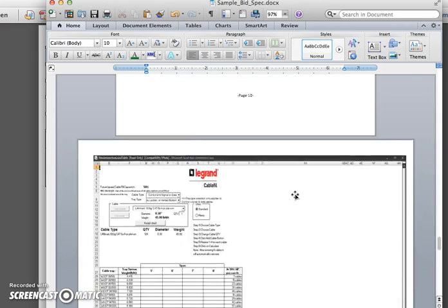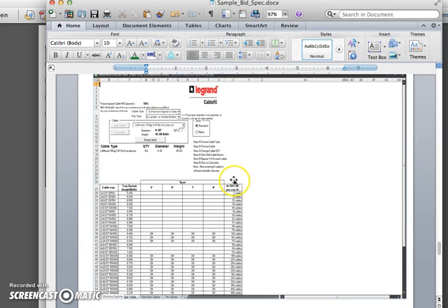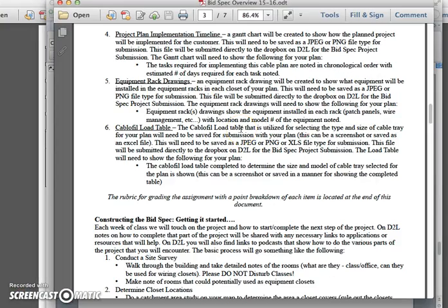And this student, I believe, had it, actually it's right here. Here's a copy of their Cablofil load table. They just did a screenshot of it to show this is all the cabling in the tray. These trays are not large enough. These down here labeled OK are large enough or strong enough to support all the cabling. So they did a quick screenshot of that to show they did that step. That's fine. That's more than adequate. So we would need to make sure we include that in our submission as well.